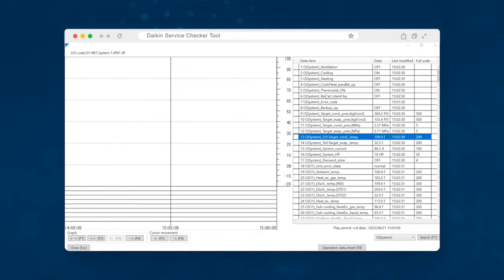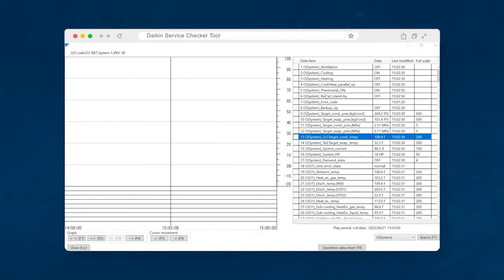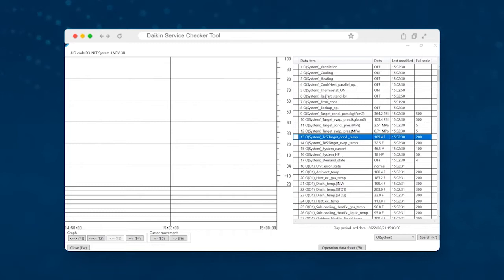So fortunately, this system presented a UO error code, which indicates that it had a shortage of charge. So it kind of gave us a hint, but that's not always going to be the case. Sometimes you might have a system that's running low on charge and nobody knows it. Maybe the system is able to maintain set point, but the system isn't necessarily operating safely or as efficiently as it should be.